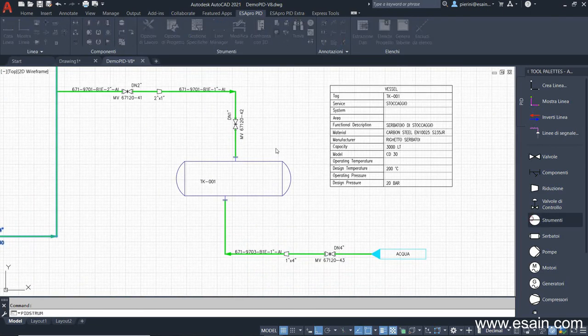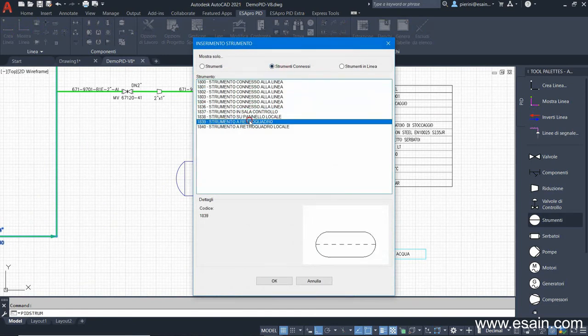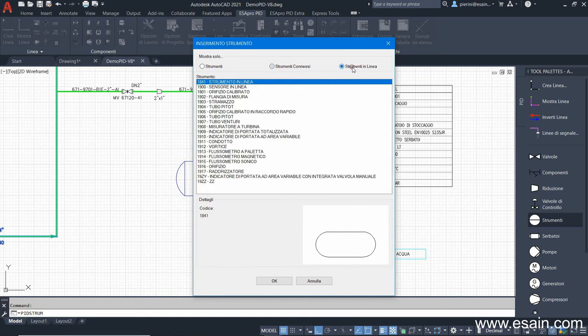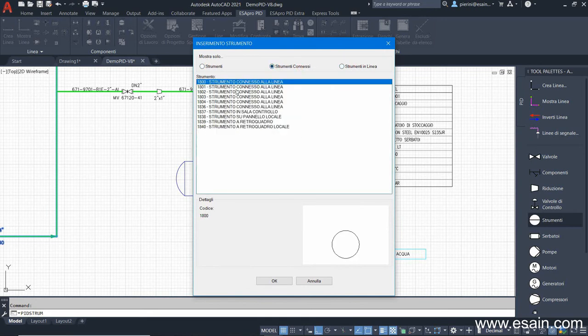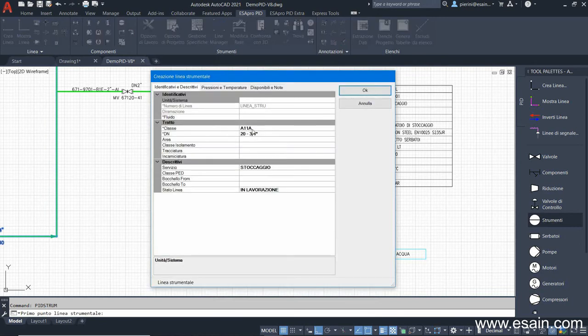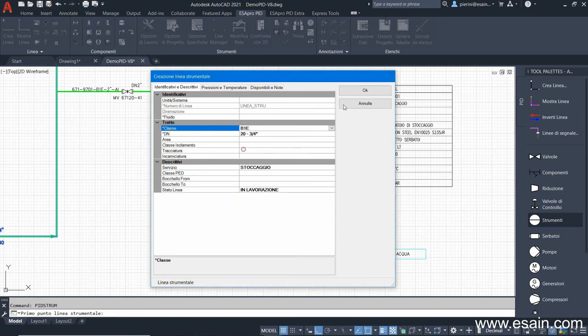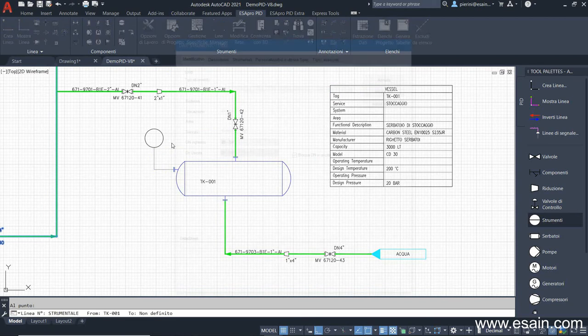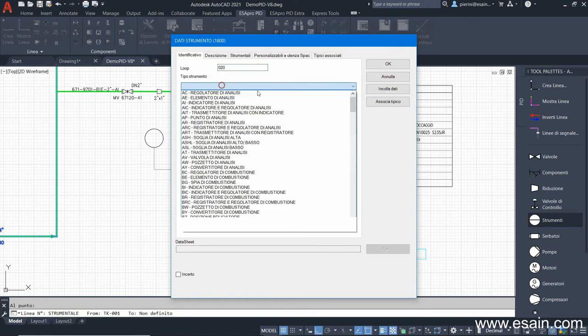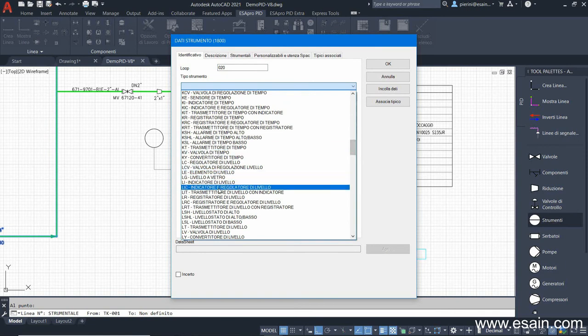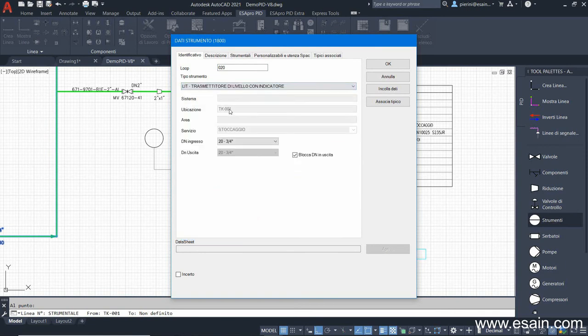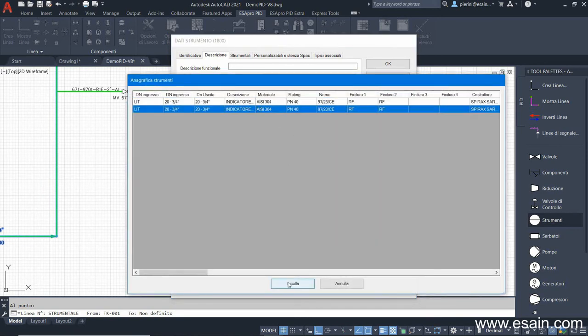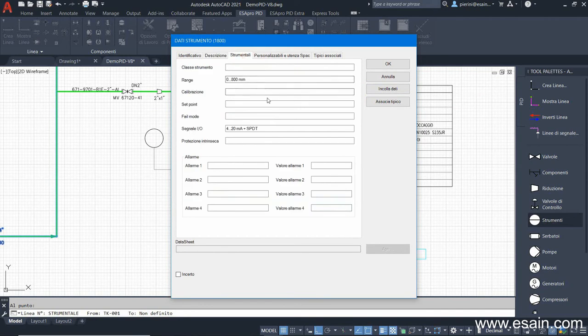Now let's get to the instruments part. We're going to create a level control loop on the tank. We have different kinds of instruments: those directly connected to the equipment or the discrete ones. Choose a connected instrument. This generates a tubing with its own diameter and class. Place the instrument and assign a loop number, in this case 020. Select the instrument function: level indicator and transmitter. The location is taken automatically and I specify the physical characteristic of my instrument. In this case, I can use paste data to feed my fields from an Excel file, and that can also be integrated if necessary. Here we have very useful technical data for electrical design.